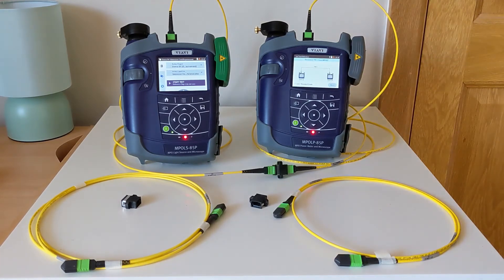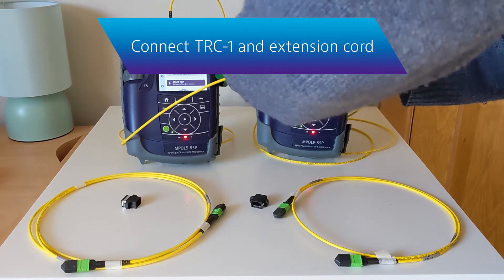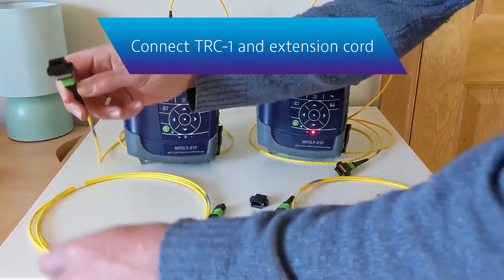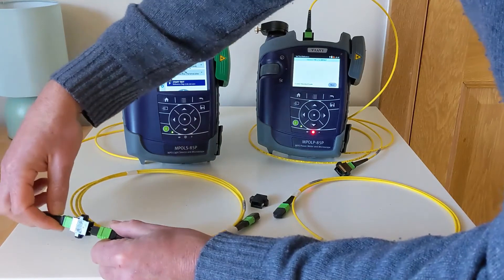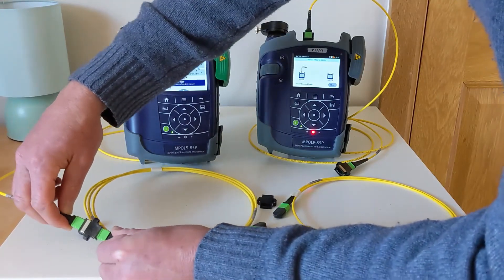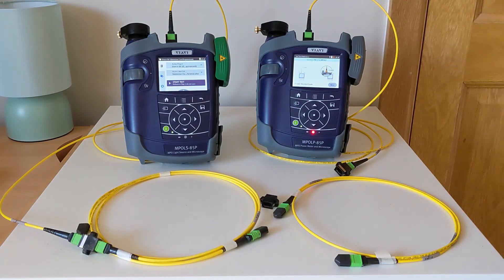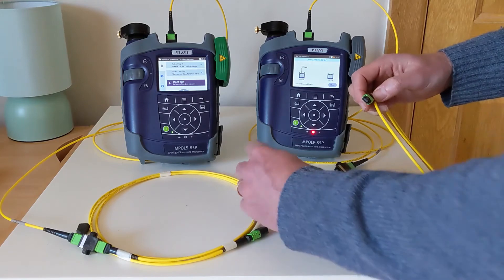Now we're going to disconnect the TRCs from each other and connect the free end of TRC1 into the extension cord using a reversed key adapter. Now that we've got these three cords, effectively we have our test assembly complete, but we want to do another verification test to make sure they are all still good. We're taking our unpinned cord and installing it in between TRC1, TRC2, and the extension cord.